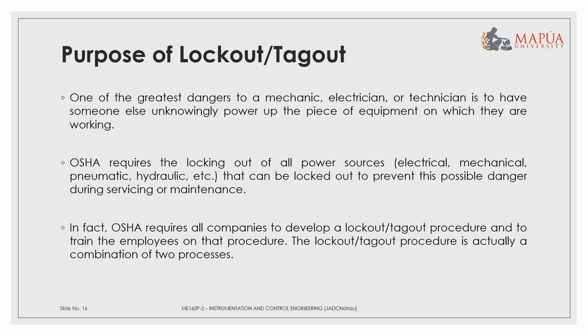one of the greatest dangers to a mechanic, electrician, or technician is to have someone else unknowingly power up the piece of equipment on which they are working. OSHA requires the locking out of all power sources, such as electrical, mechanical, pneumatic, hydraulic, etc., that can be locked out to prevent this possible danger during servicing or maintenance. In fact, OSHA requires all companies to develop a lockout-tagout procedure and to train the employees on that procedure.